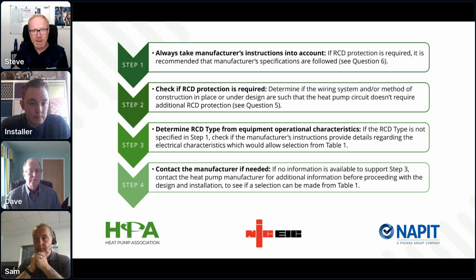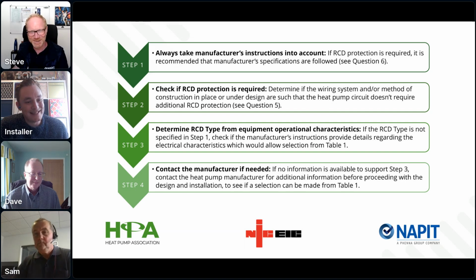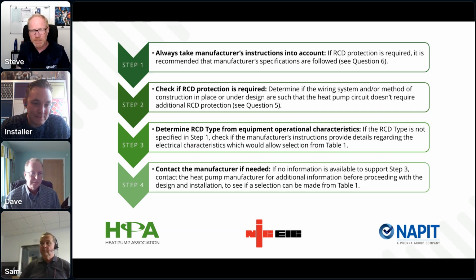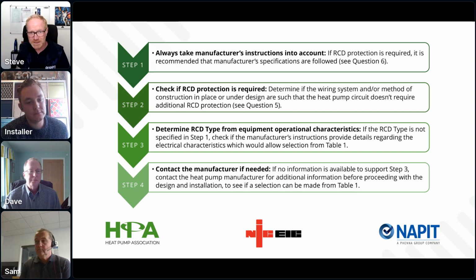So in some circumstances, perhaps where the cable supplying the heat pump is on the surface of the wall, could be clipped to the external wall rather than embedded in any fabric of the building, this could be another reason where an RCD is not required. But then we've got the other side of the coin where we say, however, manufacturer's instructions must be taken into account. So, you know, we're in a weird world where on one hand we can say that it might not be needed, but this is where the designer and the installer's got to look at the whole picture and say, is the manufacturer's instructions talking sense? Does it comply with what we've just talked about in BS 7671? And is the actual installation, the design, when I've done a survey, something that maybe negates the need for an RCD? So there are circumstances where they might not be needed.